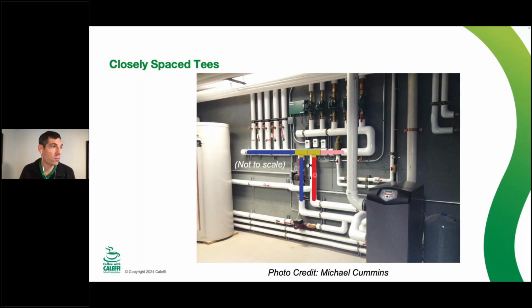And this job is a really great example. It's hard to see without the insulation here. This may be right at the edge of 4 pipe diameters apart here. So this might just be a tiny bit out of tolerance. Maybe not, it's hard to tell, but that's where things start to drift a little bit. So you take up a little bit more space here, and you might just be influencing a little bit of flow from the left side to the right side of the equation here. This system will work fine, I'm sure, but that's where we start to drift out of tolerance a bit.